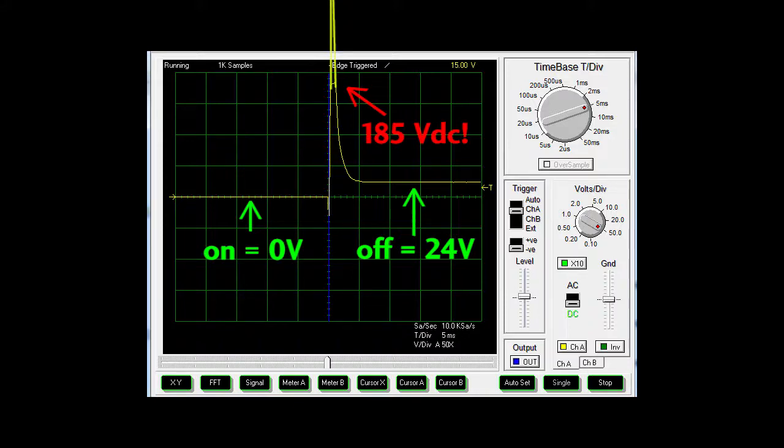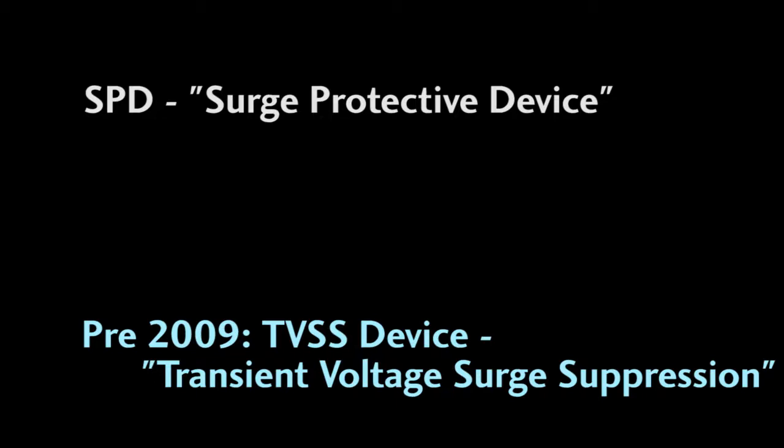So how do you get rid of that voltage spike or surge as it's properly called? With an SPD, a surge protective device. By the way, before 2009 these were called a TVSS device or transient voltage surge suppression device. That term isn't considered proper anymore, but you will still see it used.